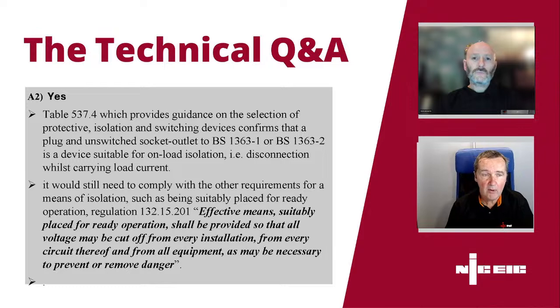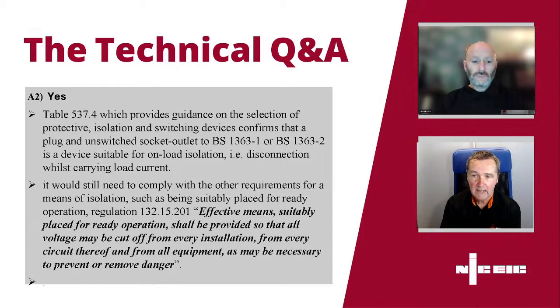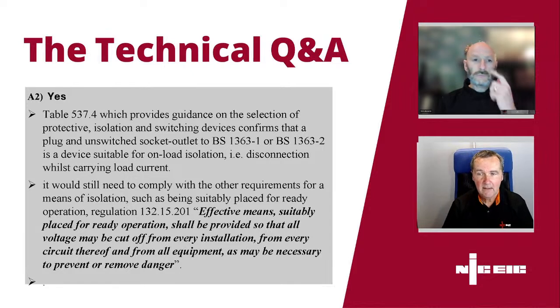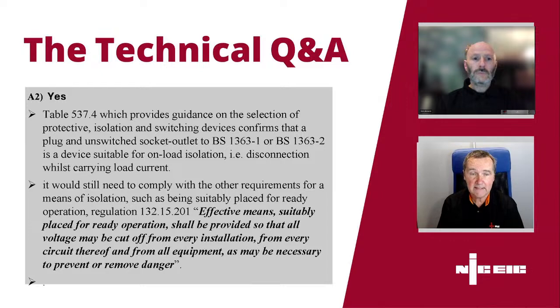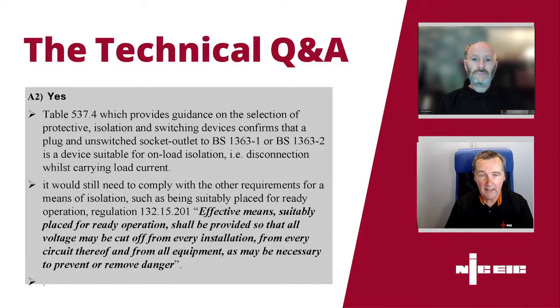You still need to comply with the other requirements of isolation, and in particular there's a fundamental regulation that says it must be suitably placed for ready operation. So you have to think about whether it really is suitably placed, so that you can use it to cut off all voltages from that item of equipment. But if you need to pull the equipment forward first just to get at the plug, then you have to question whether that's really suitably placed for ready operation in an emergency, or when you want to remove danger. So yes, a plug can be used, but it still needs to comply with that fundamental requirement of being suitably placed for ready operation.